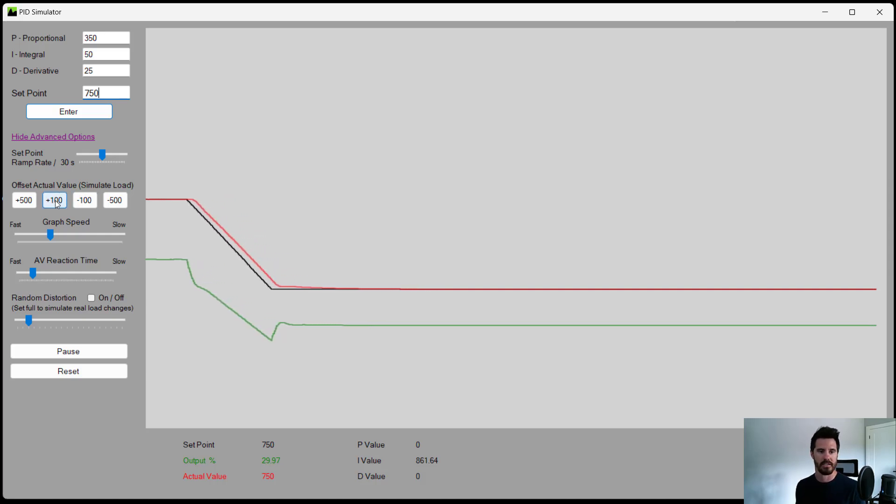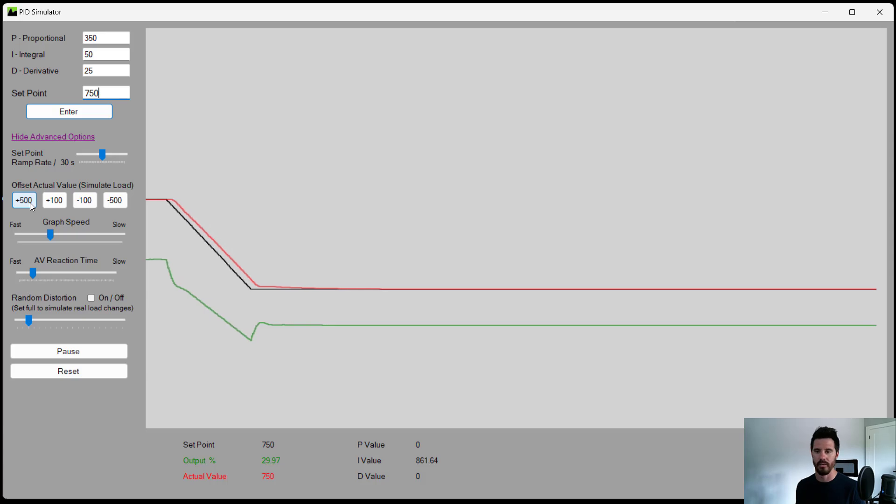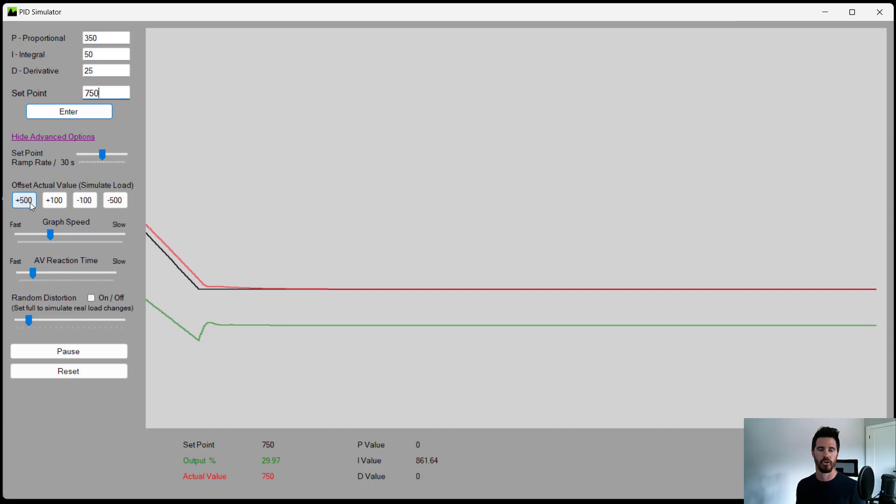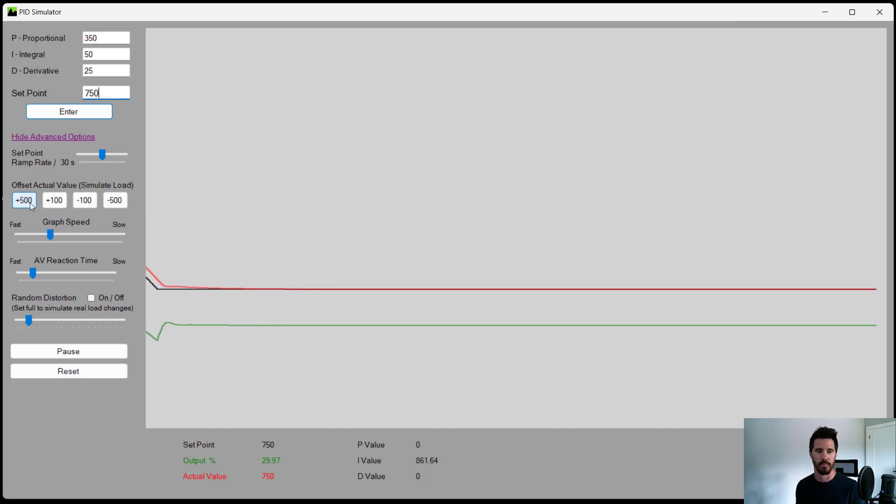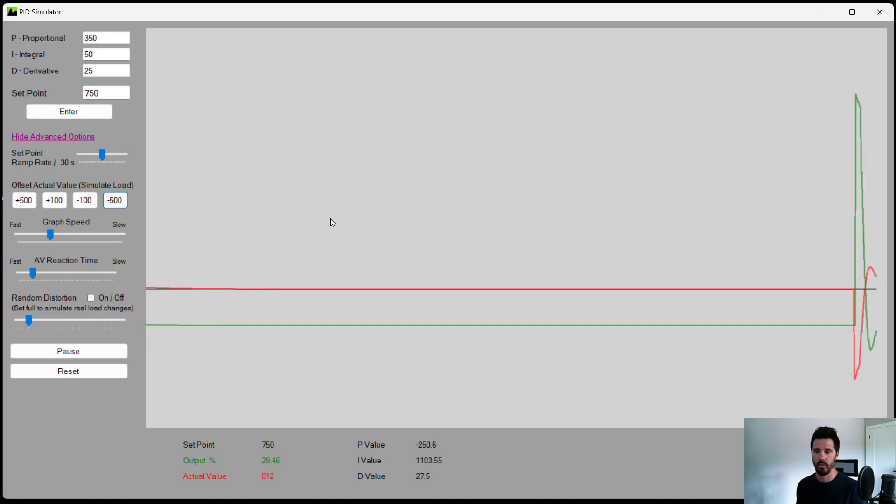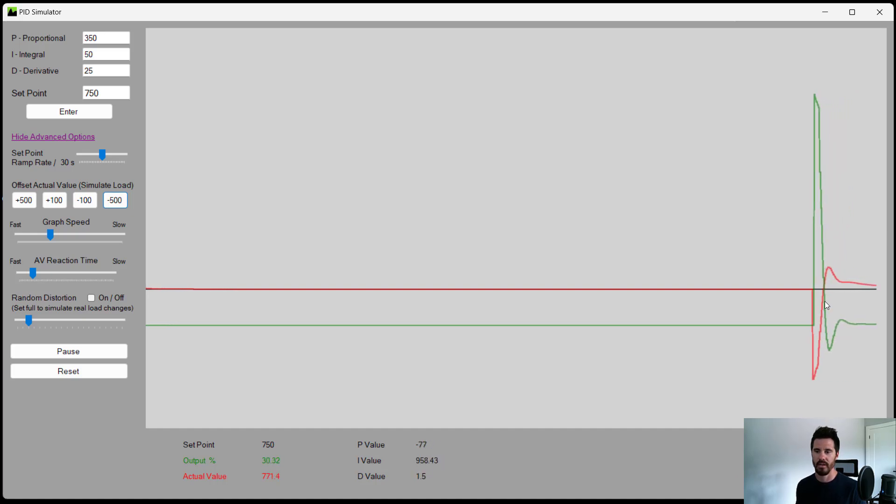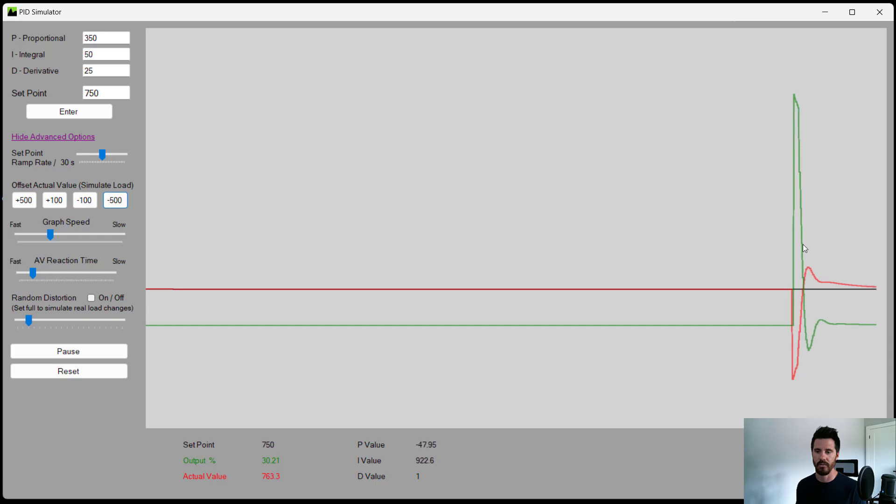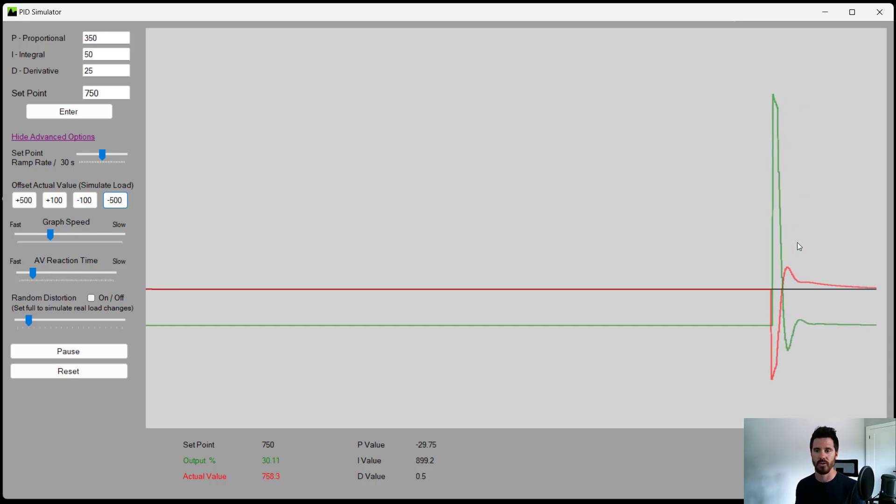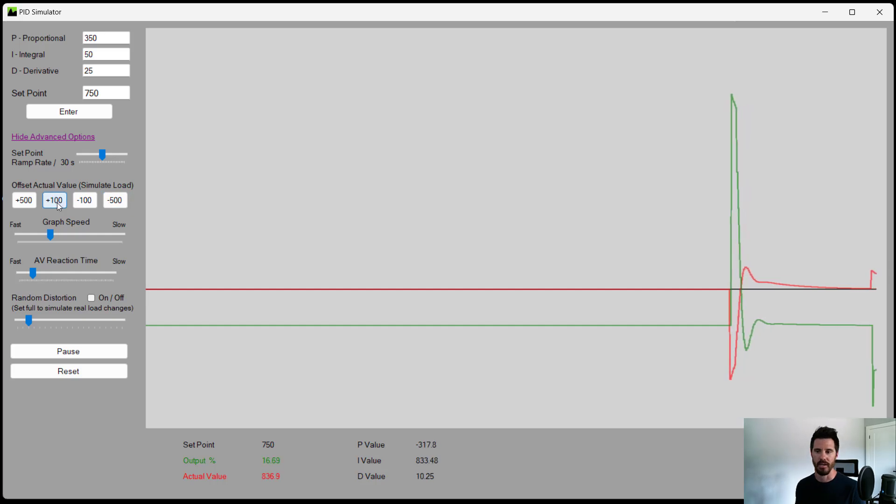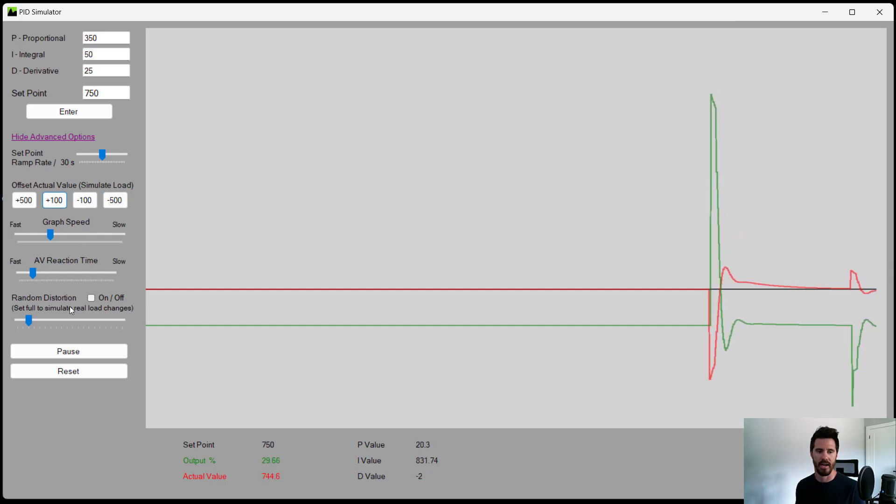The other thing in the simulator, we can offset the actual value. So let's say it's a temperature control loop and somebody opens a valve and the temperature drops suddenly. We can hit it with a big drop in load and then see how the actual value and see how the output affects the actual value to bring it back to that set point. We can increase the load and see how it reacts to that.